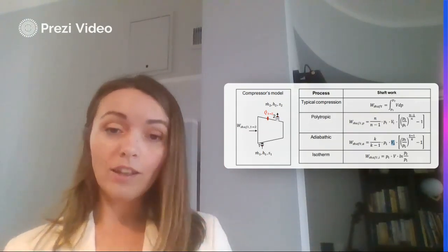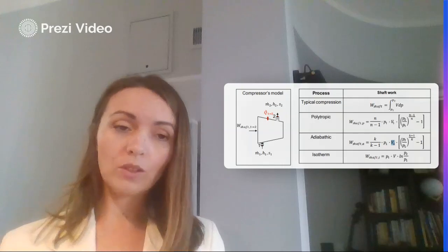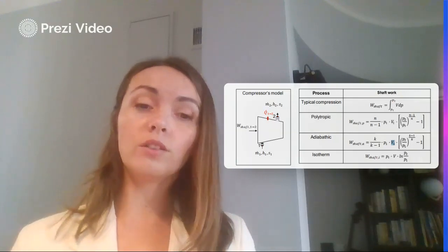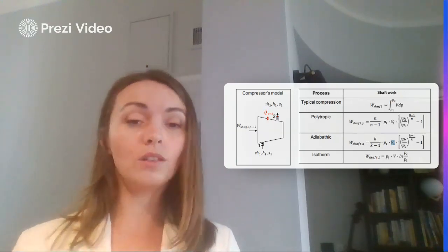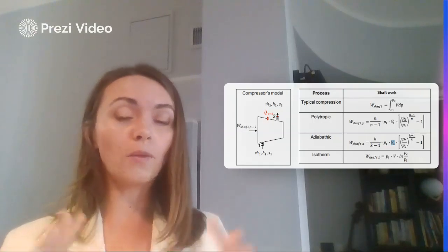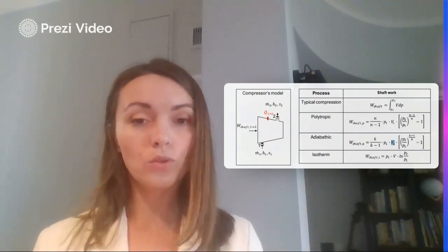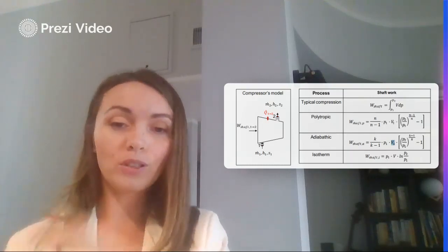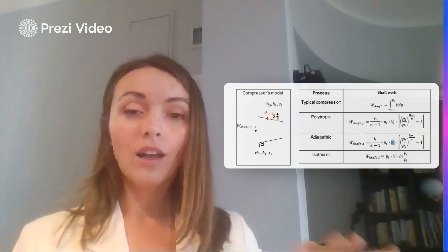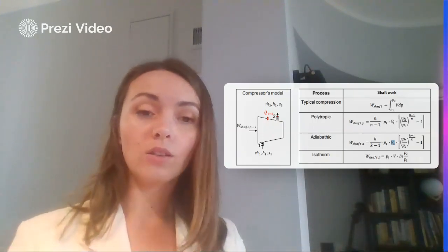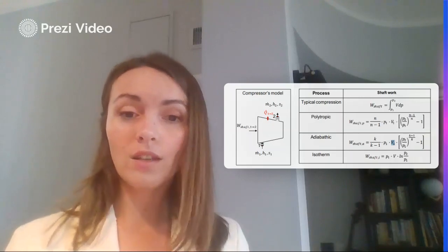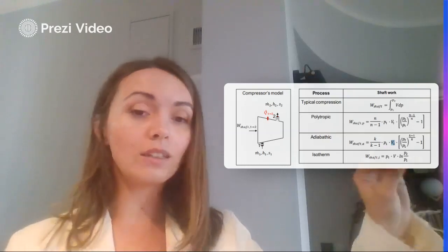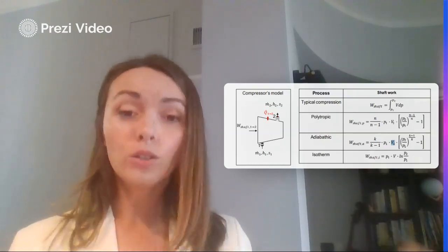However, this is not yet the efficiency of compressed air. To calculate the efficiency of compressed air, we need to see the exergy balance. The exergy balance covers the full energy transformed from electrical and mechanical work into technical work, enthalpy change, and heat. We then need to see what part of the heat and technical work — the enthalpy — is dissipated. The rest is the useful energy of compressed air, later used for processes. This is essentially the thermodynamic performance of the system.